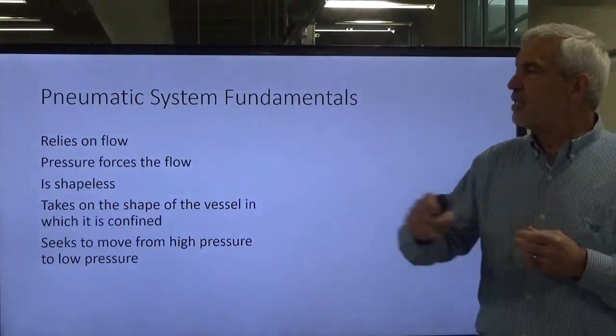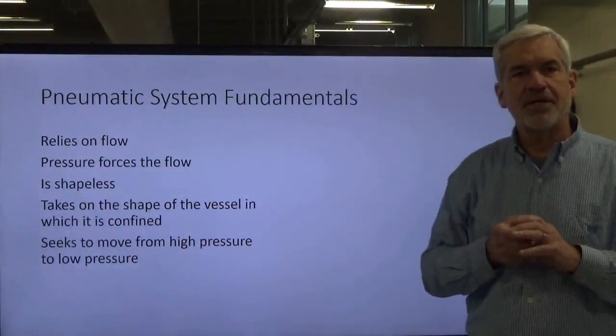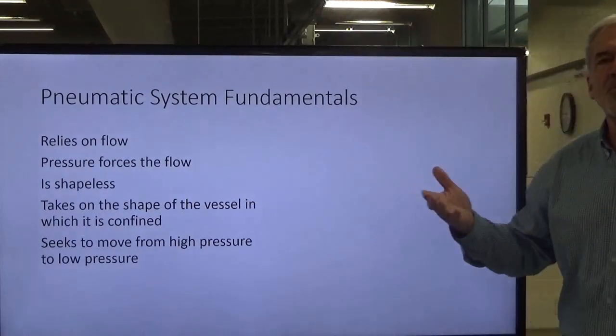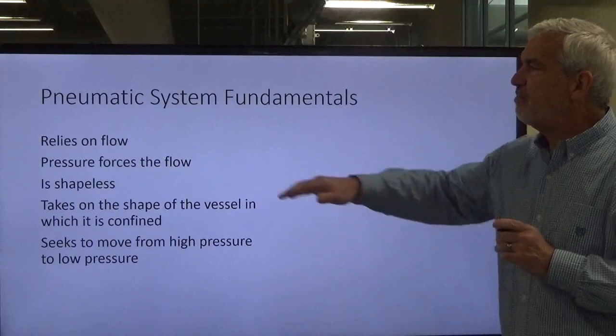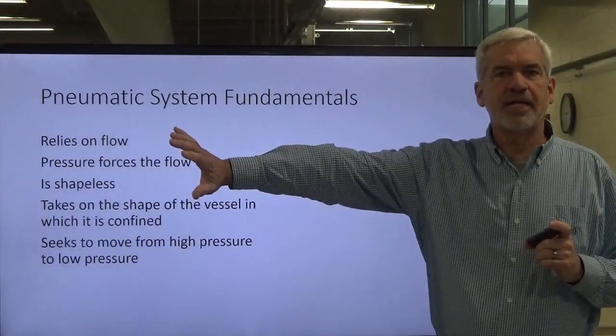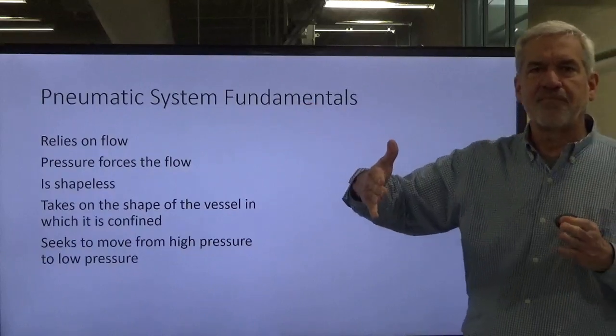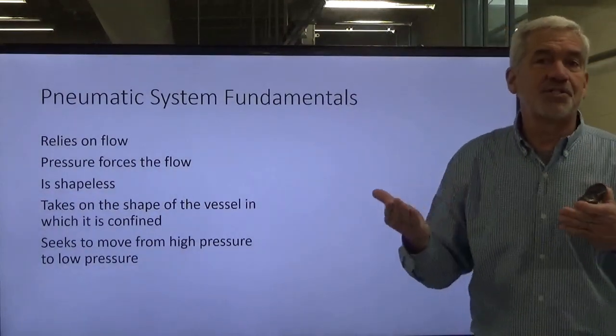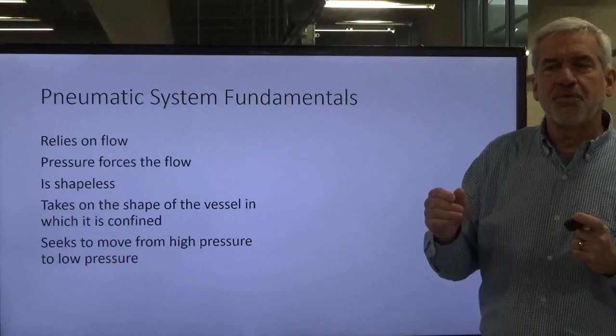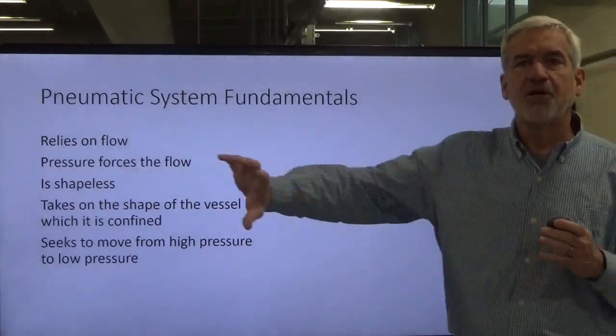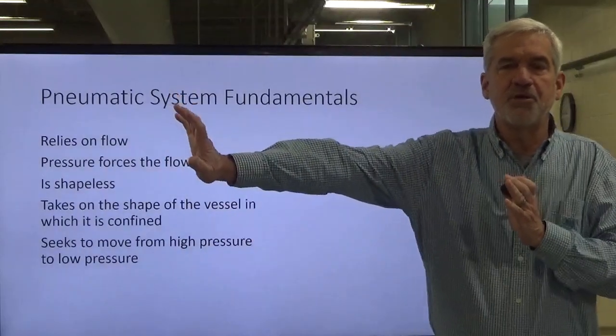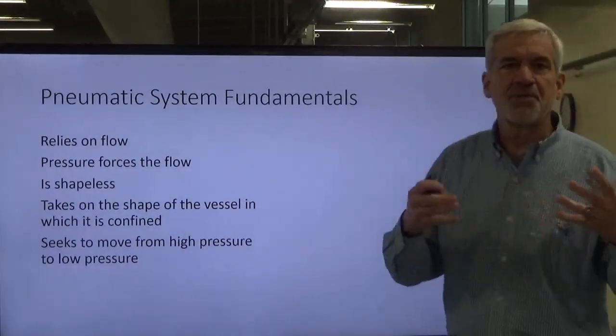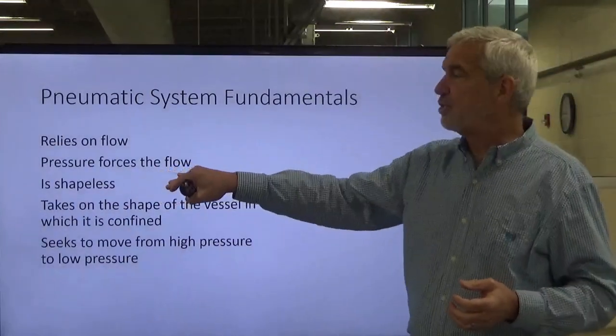A couple of fundamentals about pneumatics: it relies on flow. A lot of people think you've just got to have pressure. But what we want to do is move that gas — and for the most part we're talking about compressed air. It's one thing to have pressure, but when you have pressure, that means you've either got a restriction of flow or no flow at all. So get it in your head: we're not trying to create pressure in a line, we're trying to create flow. You do use pressure behind the flow to move it at certain rates, but we are looking at flow.